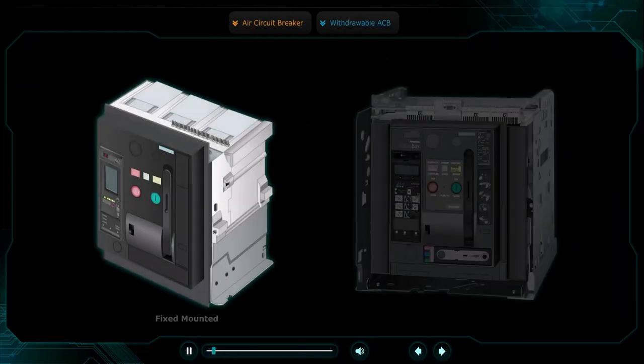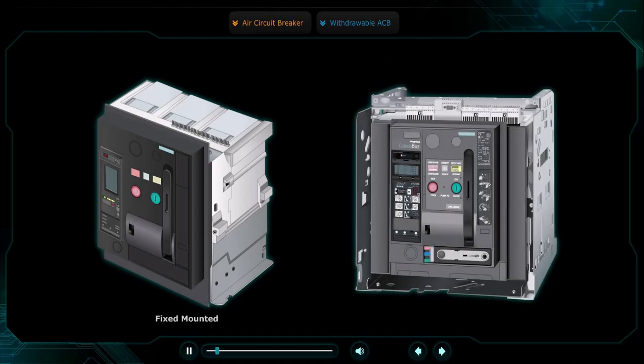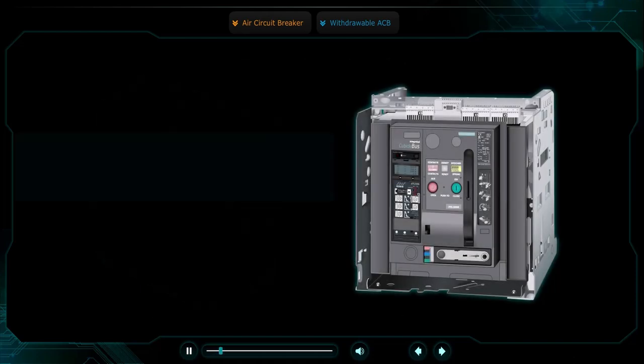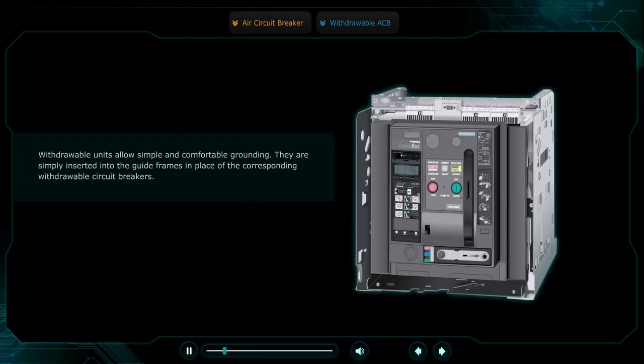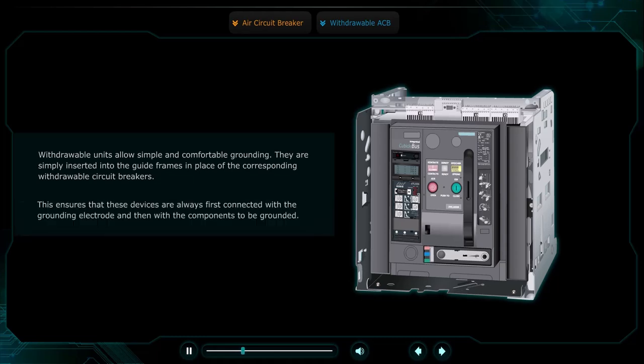Air circuit breakers have two versions: fixed mounted version and withdrawable version. Withdrawable units allow simple and comfortable grounding. They are simply inserted into the guide frames in place of the corresponding withdrawable circuit breakers. This ensures that these devices are always first connected with the grounding electrode and then with the components to be grounded.